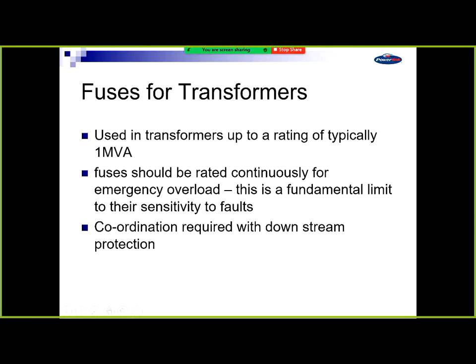What was that last comment I had in there? Is that one? You need to coordinate with downstream protection. So utilities need to be looking that their fuses grade over top of one another. If you've got transformers and then another transformer beyond that, or another feeder beyond that, you've got to grade all your lines of protection. For us, it's not an issue with a local supply. We come at 11 kV off the smaller transformers, 19.1 off the bigger transformers, down to 415 and around in the substation. So there is no grading downstream for us.